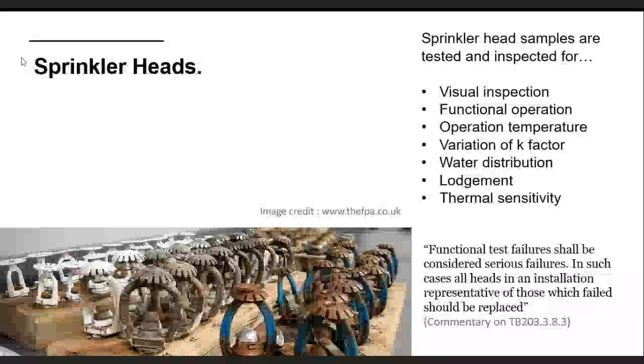But if you do find some concerns, then you might want to test some more heads. It says functional test failures shall be considered serious failures. In such cases, all heads in the installation representative of those which failed should be replaced. So you've got a scale really. If you find serious issues with the heads that you've tested, then all the heads in the sprinkler system, or in the installation or in the zone, are going to have to be stripped out and replaced. If you can pin it down to a particular location, then you wouldn't necessarily have to replace them all. But as I said, in some ways that's a grey area. There is more information in the standard, but I think there would also have to be some consultation between the various parties as to what action is then required.